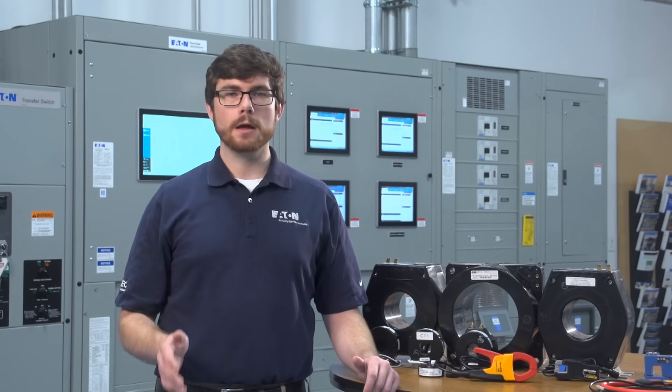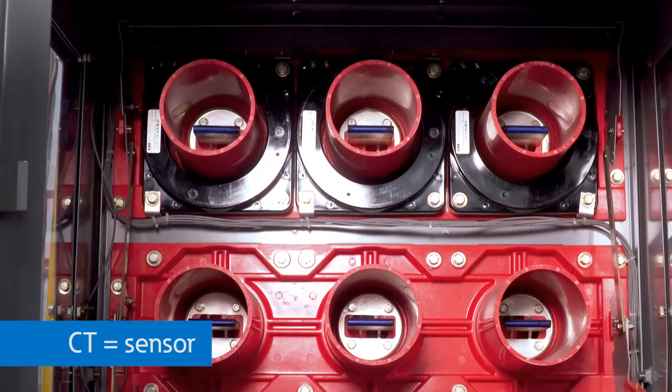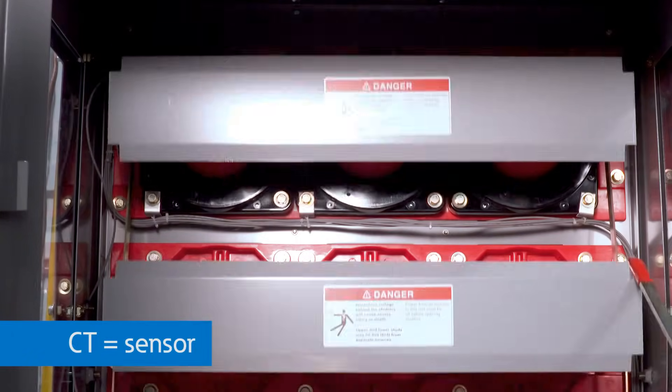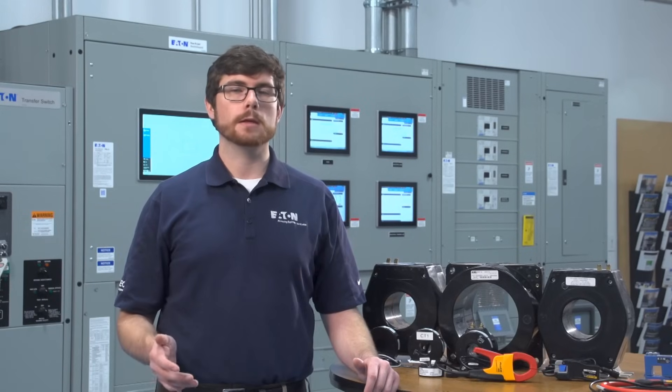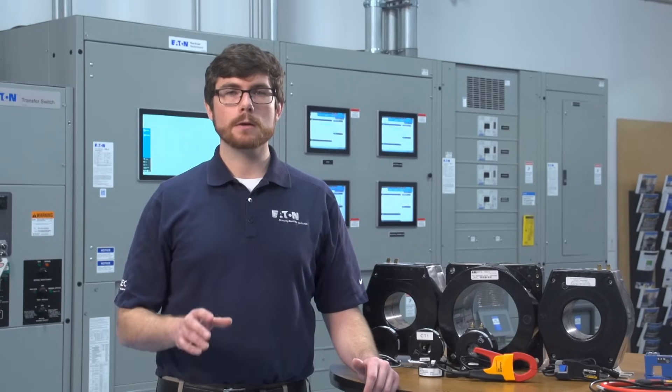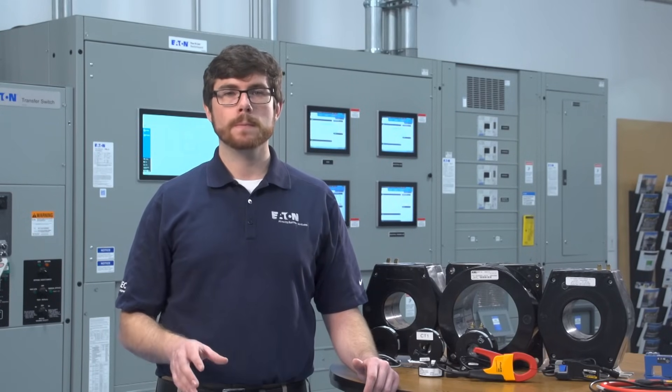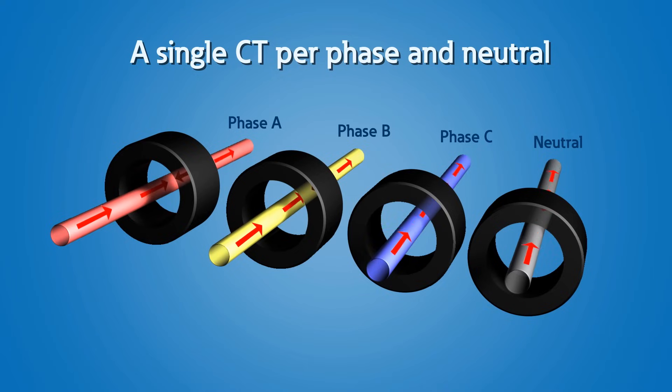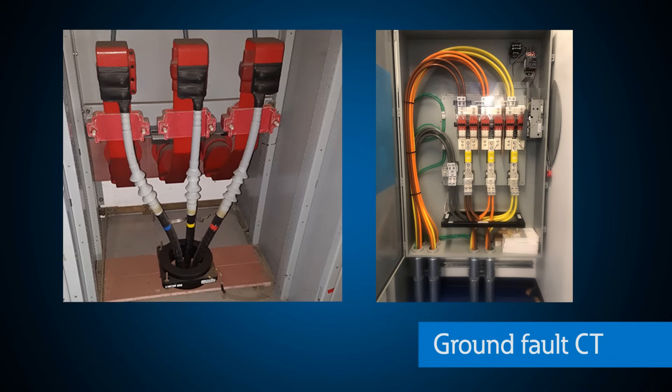Many circuit breakers have built-in CTs used to monitor current. As a point of clarification, a lot of people call CTs sensors when they are mounted inside switchgear or circuit breakers. But the functionality and purpose is the same, to get current measurements to a useful level. A single CT is generally needed for each phase and neutral to monitor current, but for ground fault protection a special type of CT is used.